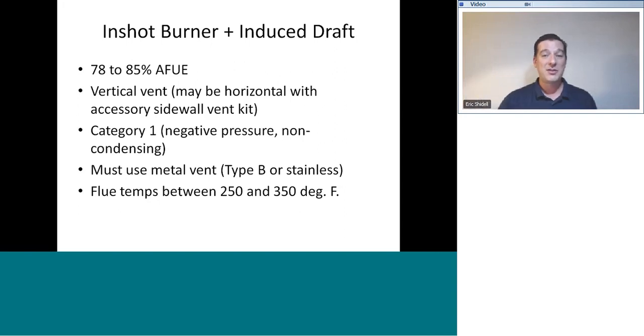So when you're out on a service call, be especially skeptical of a sidewall vented 80% AFUE gas appliance. They're quite rare because they were a lot more expensive to do that way. And so many of the ones that I have seen done that way were done not by the book. They were done essentially illegally because that's not an approved method of venting for those appliances.